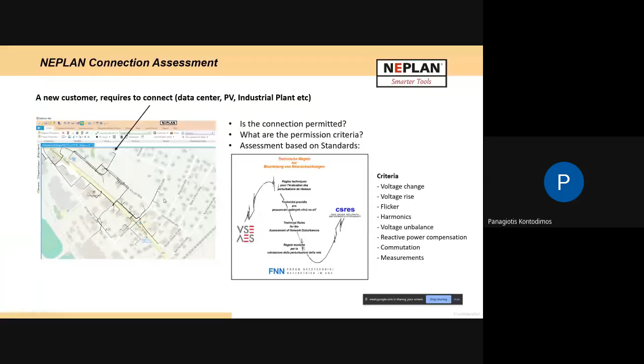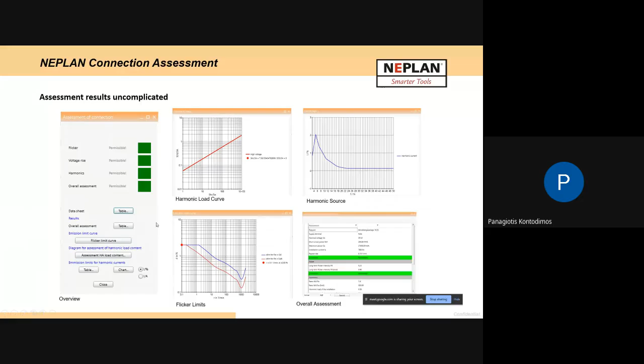There are some other modules, for example connection assessment. I'll go quickly here because this is more related to some standards, especially in European countries, when they want to connect a new photovoltaic, or a new industrial customer. Then the utility has to assess if this connection is okay in terms of some well-defined criteria. For example, we can make a quick assessment for flicker, voltage rise, harmonics, and overall assessment. This is offered as a module for quick assessment, but of course all of these can be done one by one. Anyway, this is the connection assessment module.